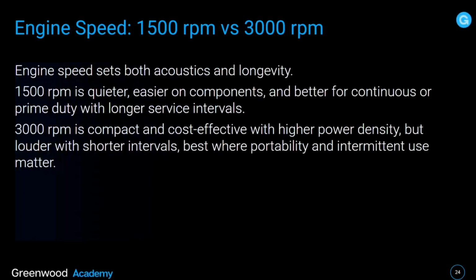Now, engine speed sets both acoustics and longevity. 1500 RPM is quieter, easier on components, and better for continuous or prime duty with longer service intervals. 3000 RPM is compact and cost-effective with a higher power density, but louder with shorter intervals, and it's best where portability and intermittent use matter. In other words, not for a situation where a prime rating is required.